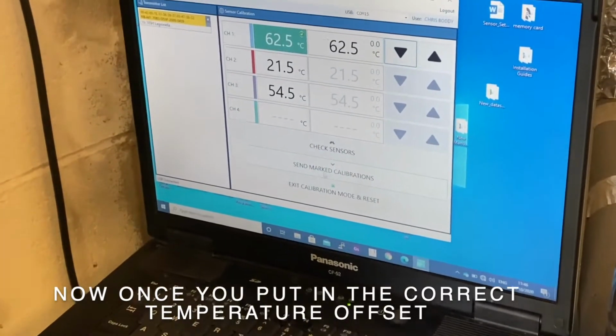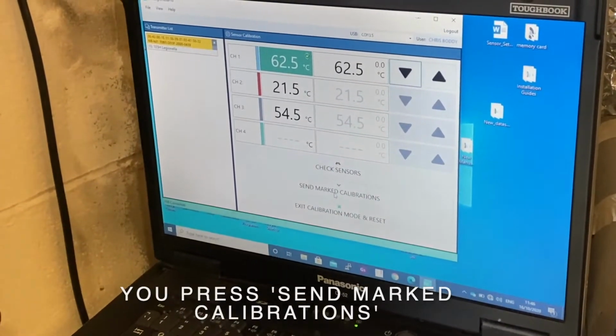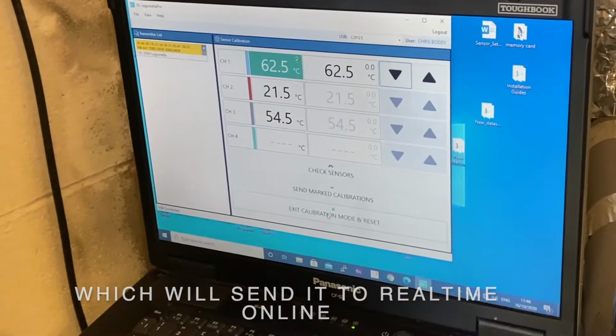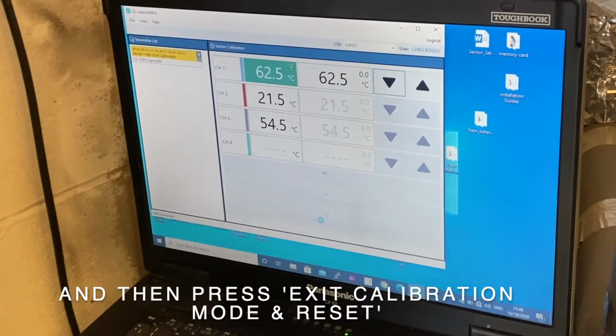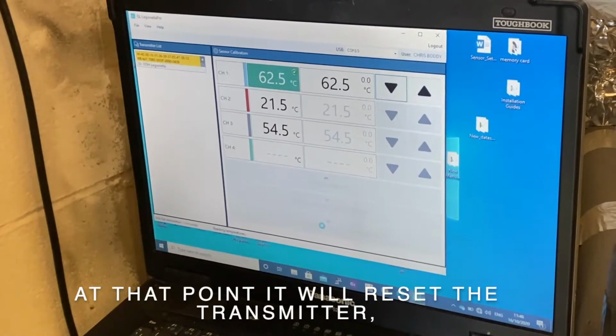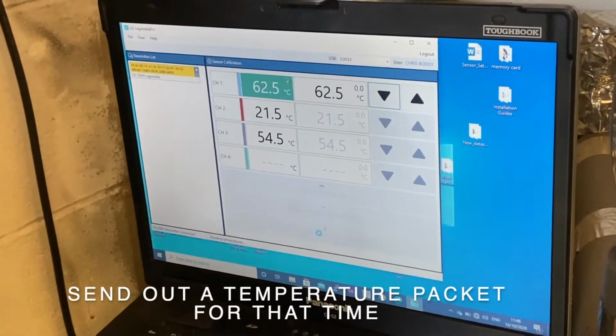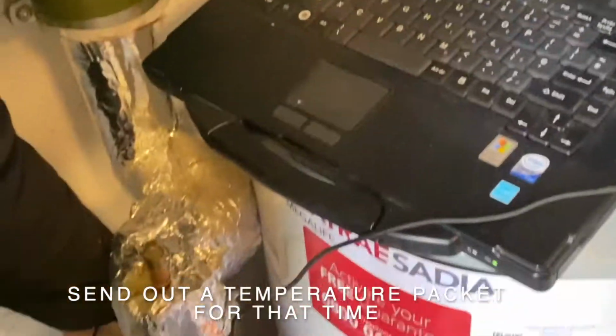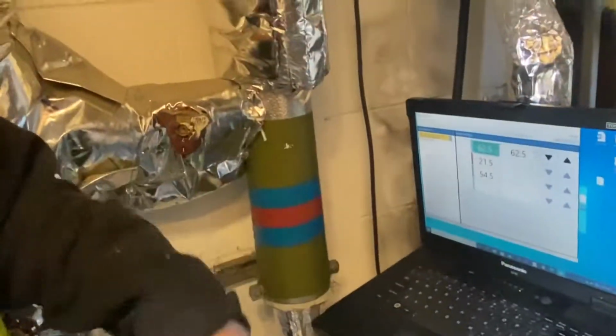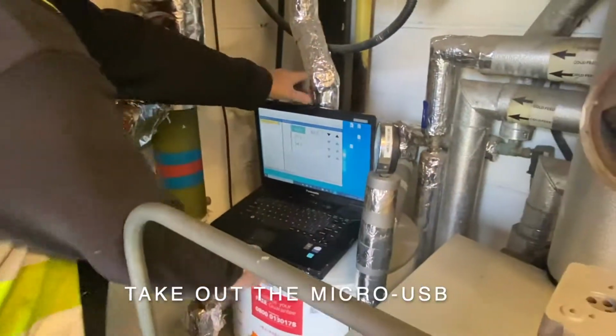Now once you put in the correct temperature offset, you press send marked calibrations, which will send it to real time online, and then press exit calibration mode and reset. And at that point it will reset the transmitters, send out a temperature packet for that time, so whatever reading it reads at that time. Take out the micro USB.